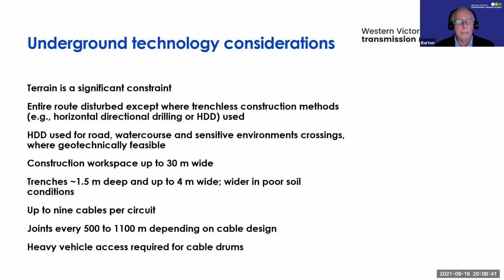The trenches are similar in that they are about 1.5 metres deep. The reason they are about that deep is that in both HVAC and HVDC, we want to achieve ultimately about 1 metre cover over the cables. If we go deeper, the thermal dissipation of heat generated by the cables becomes more problematic, and to overcome that, sometimes you need to go to a much heavier cable, which increases cost. The trenches are narrower, typically around 1 to 2 metres wide, to accommodate a single HVDC link or circuit.